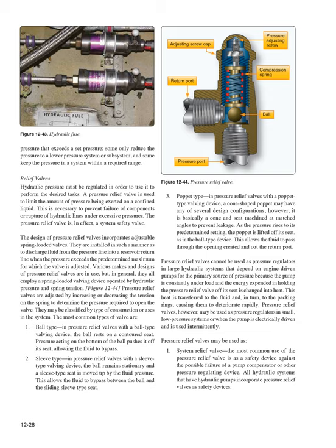Various makes and designs of pressure relief valves are in use, but, in general, they all employ a spring-loaded valving device operated by hydraulic pressure and spring tension. Figure 12-44, pressure relief valves are adjusted by increasing or decreasing the tension on the spring to determine the pressure required to open the valve. They may be classified by type of construction or uses in the system. The most common types of valve are, 1. Ball type. In pressure relief valves with a ball type valving device, the ball rests on a contoured seat. Pressure acting on the bottom of the ball pushes it off its seat, allowing the fluid to bypass.